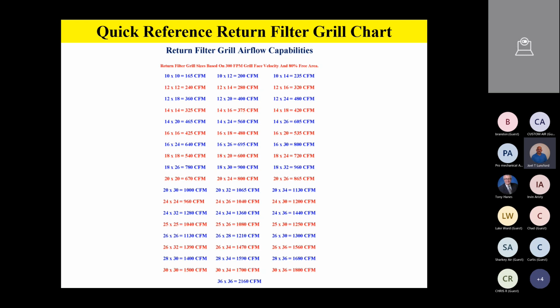But if you go to Hart and Cooley or whatnot, and you look at a particular return grill and it says K of A or K of C, which is the free area, and it says 0.95 or 0.92 or 0.89 or whatever, you would substitute that for the 0.8 that I have for free area in the formula. However, I want to really, really stress something. Even though a return grill might be rated for 500 FPM of face velocity, that is not with a filter in there. Manual D, even though you might have a Hart and Cooley return grill that says our recommended face velocity is 450, if you put a filter in that grill, then it goes back to that 300.